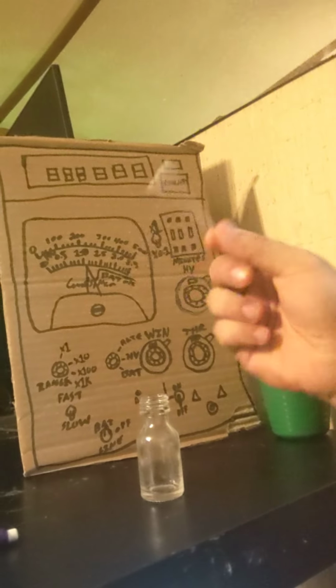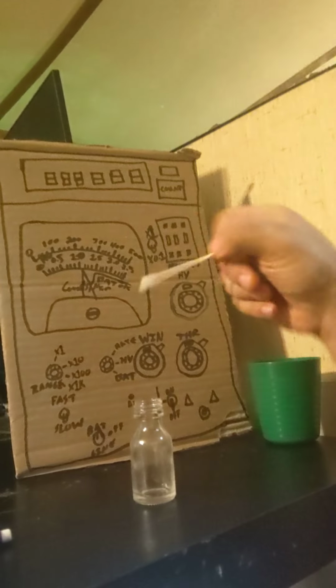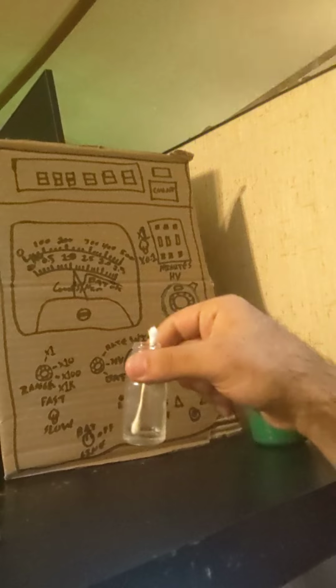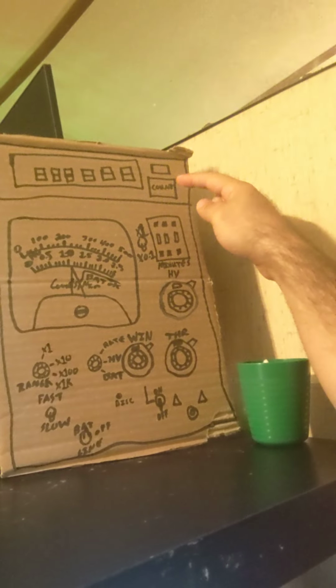So first thing, we have to take our cotton swab out of the test tube and get a background radiation reading. So we'll just simply take it out, kind of swirl it around in the air, and get all that background radiation. Put it back in our test tube there. And then we're going to stick this into the well counter. Once you place it into the well counter, you see up here on the spectrometer how it says count. That's how you start determining the CPM. So we're going to hit count. And now we just wait for it to be finished. Alright, it's over. So we're going to take this out, set that to the side. Looks like we got 300 CPM for our background.